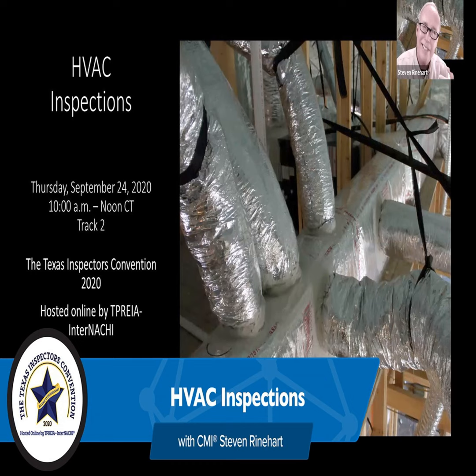Grills, registers, usually what you see, they just get dinged up. They're not secure to the wall, they've been bent, furniture hits them. Location of return air openings, typically, they'll prohibit it not in the kitchen. Now our kitchen is not well defined. What is a kitchen? It's open fully, a certain distance from any cooking appliances. So you're not supposed to have them in like bathrooms or places where you wouldn't want to be sharing the air from.